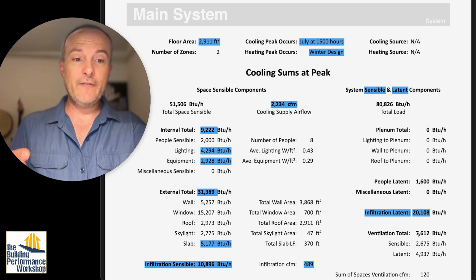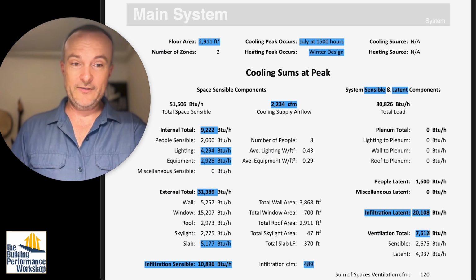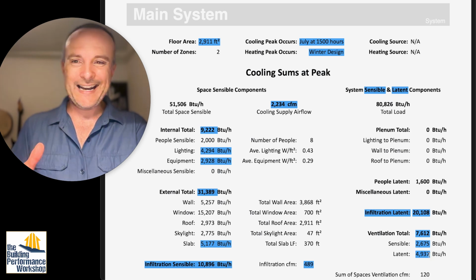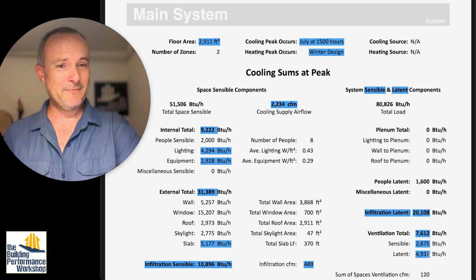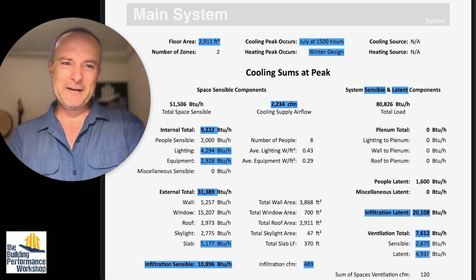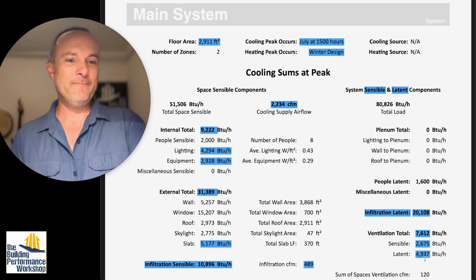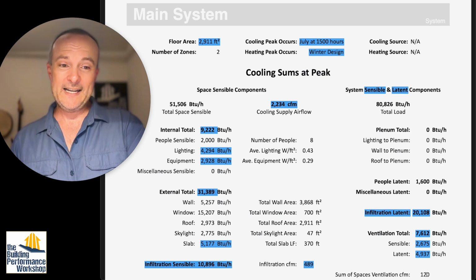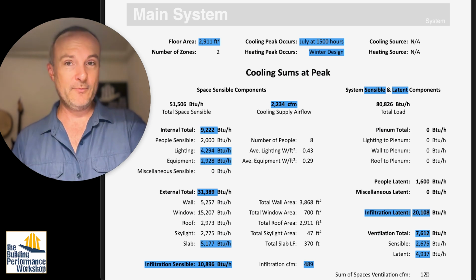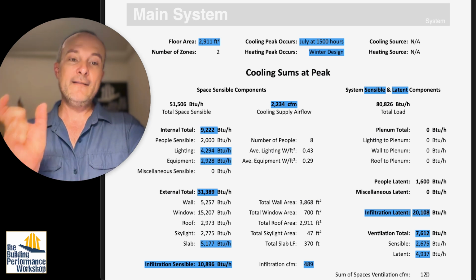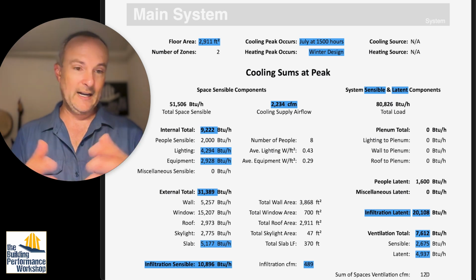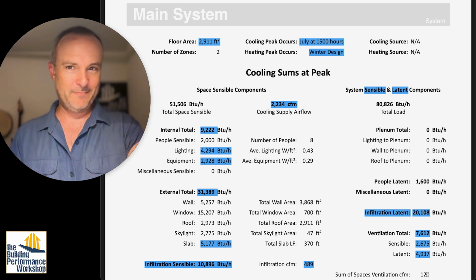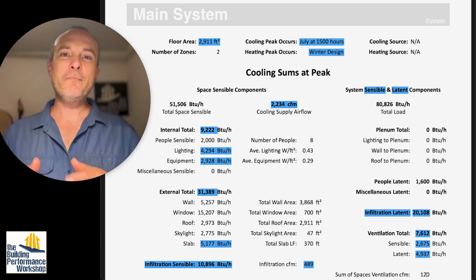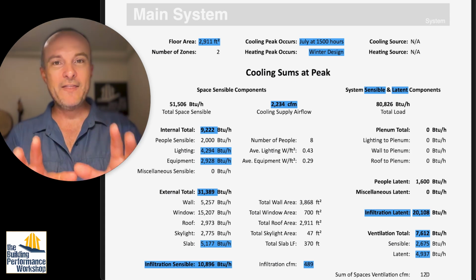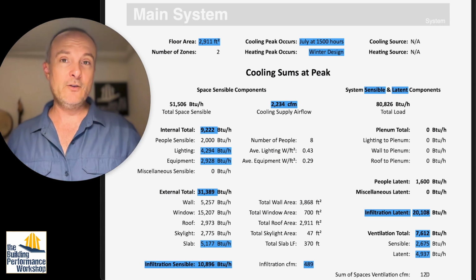Lastly, ventilation. So ventilation, we've got 7,000 BTUs per hour, 2,000 sensible, 5,000 latent. Again, I don't know where this is. Is this in the Caribbean or something where it's kind of mild temperatures, but really intense humidity? I don't know. This is only with 120 CFM. That's not an ERV, I'll tell you right off the bat. So it should say ERV on here somewhere and have a recovery ventilation. If you're going to be building tight, which these people are clearly not, and you're going to have ventilation, make sure that it says somewhere on this that the ventilation is going through a recovery core and it's recovering some of that stuff.